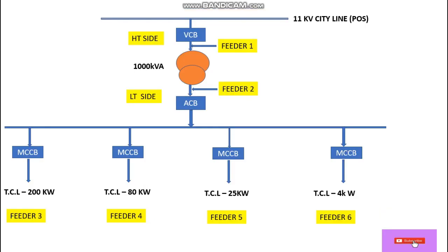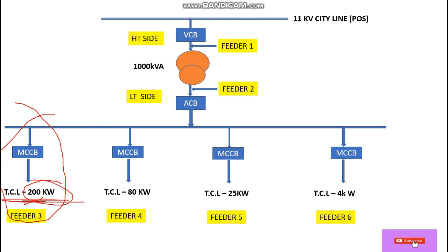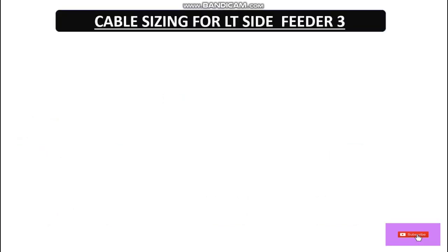In this video we will calculate the cable size for Feeder 3, which has a total connected load of 200 kilowatt. To calculate the cable size for this feeder as per this connected load, first we have to calculate the full load current.